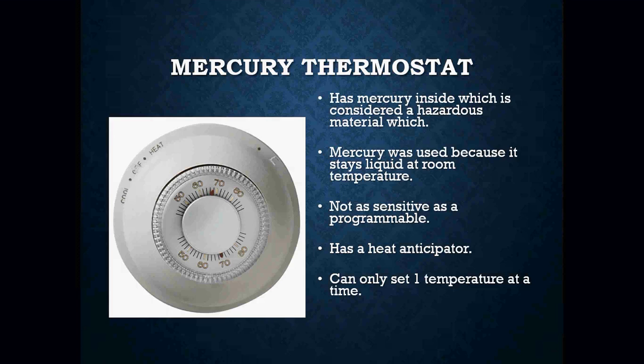The mercury was used because it stays liquid at room temperature. Mercury thermostats were not as sensitive as programmable thermostats today. They do have a temperature swing — usually anywhere between two and four degrees. They have a heat anticipator, which is used to shut a furnace off prematurely so that we don't drastically overshoot the thermostat set point. These thermostats were only used to set one temperature at a time. If you were in heat and wanted 70 degrees, you'd flip the switch to heat and turn it to 70.